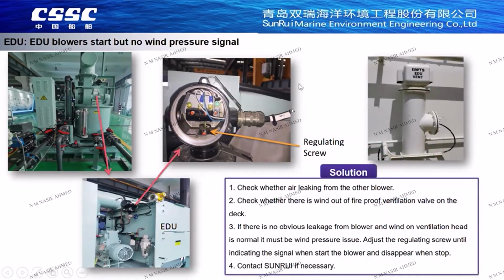In case of this problem, the first step is to check whether the other standby blower has air leakage and whether the damper baffle is closed normally. Next, manually start the blower and check whether air is blowing out of the front ventilation cap on the deck. If there is no problem with the above 2 points, there is a high probability the problem occurs on the wind pressure switch. In EDU, it is on the upper part of the blower, near the hydrogen removal pipe.